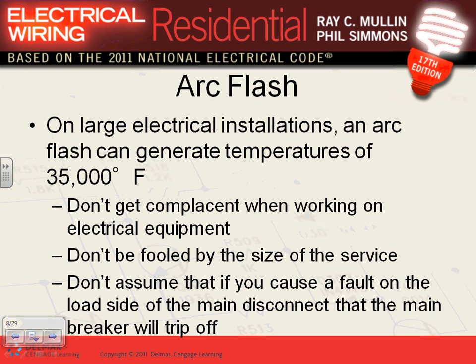So you take one phase and it arcs to the frame of the panel. Now you've got a big ball of fire. If it's a 200 amp 240/120, piece of cake, it'll be a tiny little ball of fire. If you're just wearing glasses, dressed up like me with protective glasses, guaranteed you're good. But if that was a 200 amp 480/277, very close to the transformer, the amount of arc and short circuit is huge. That big ball of fire could burn your face. Yeah, your eyes are protected, but all your face here could be burned. So keep that in mind, guys.